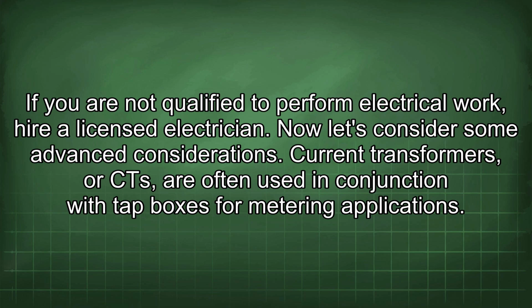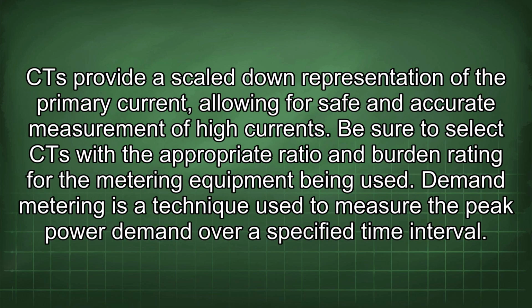Current transformers, or CTs, are often used in conjunction with tap boxes for metering applications. CTs provide a scaled-down representation of the primary current, allowing for safe and accurate measurement of high currents. Be sure to select CTs with the appropriate ratio and burden rating for the metering equipment being used.